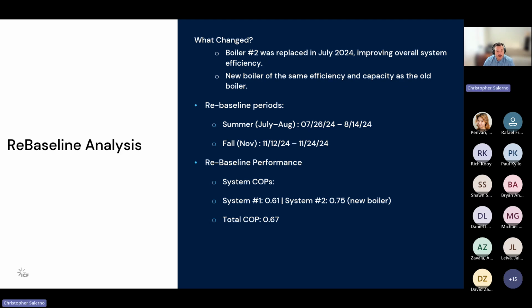So that did require a rebaseline through summer, July to August, and then to the fall. So we did get some warm weather data, including into November, which was some colder weather data, which is kind of important. So when you're rebaselining, you want to be able to get a good weather coverage. So we've tried to get some hot weather data and then some cold weather data to be able to see if the performance is closely related with the outside air conditions, or the OAT. What I mean is the outside air temperature.